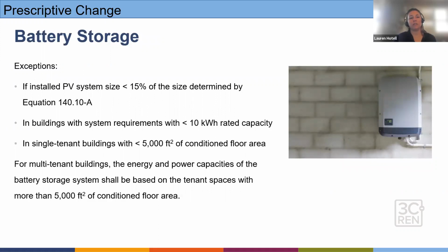Some of these exceptions include, if a PV system is too small, same as multifamily, we don't want to be installing a battery system that cannot support the PV system, or if it's just not cost effective at all. An additional exemption is single tenant buildings with less than 5,000 square feet of conditioned floor area. In multi-tenant buildings, the energy and power capacities of the battery storage system need to be based on the tenant spaces with more than 5,000 square feet of conditioned floor area.